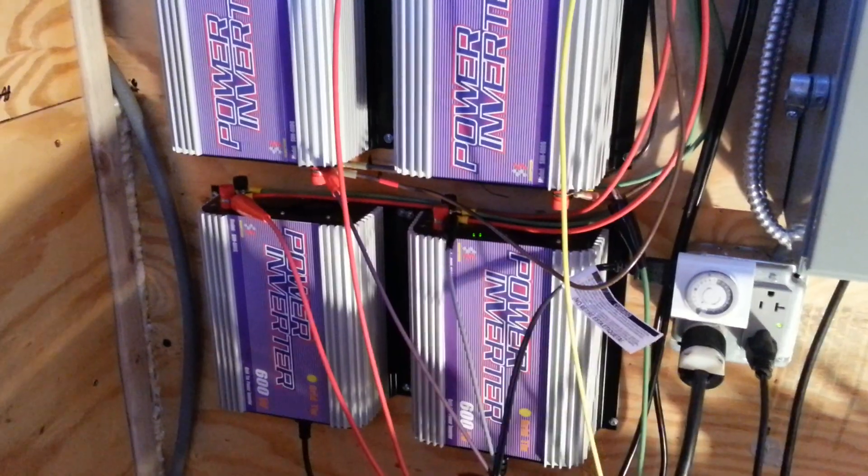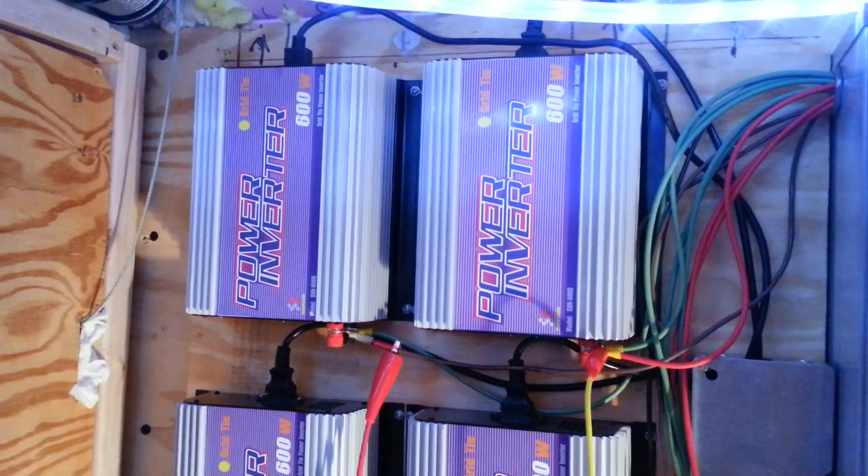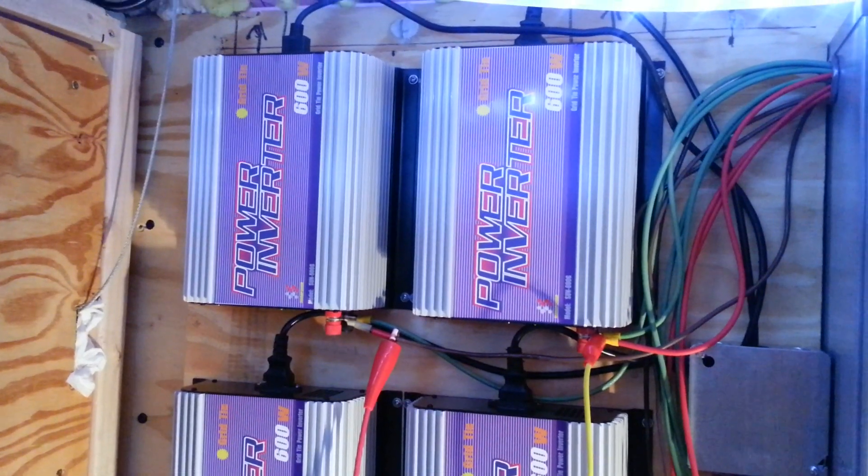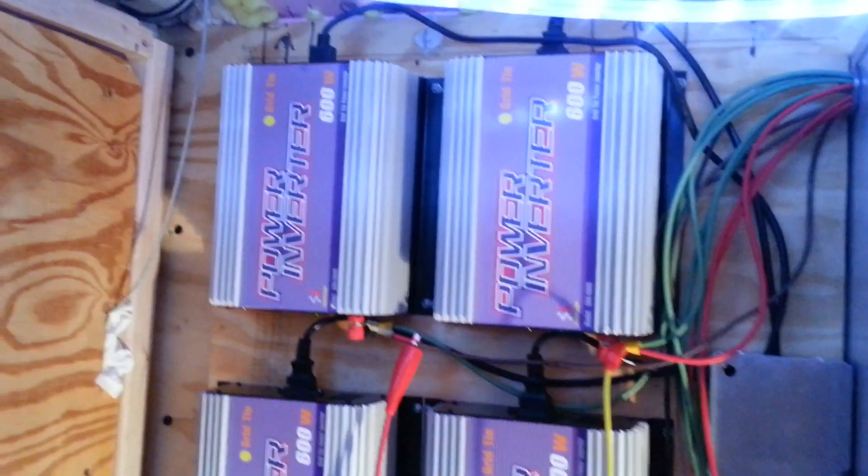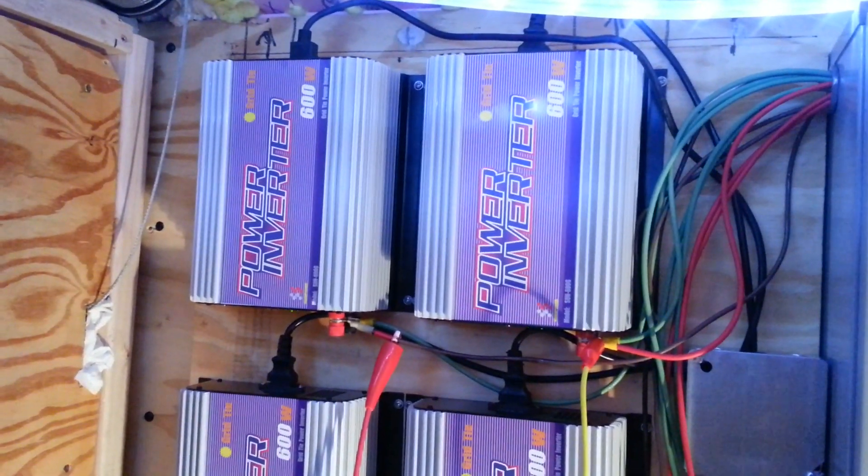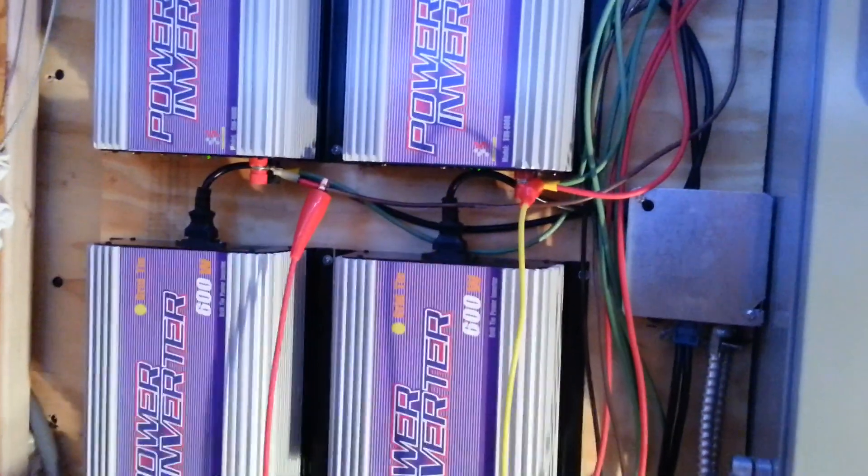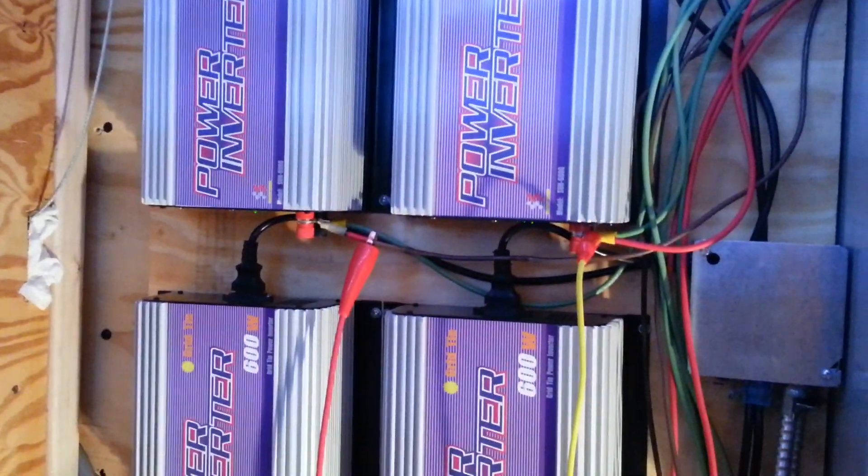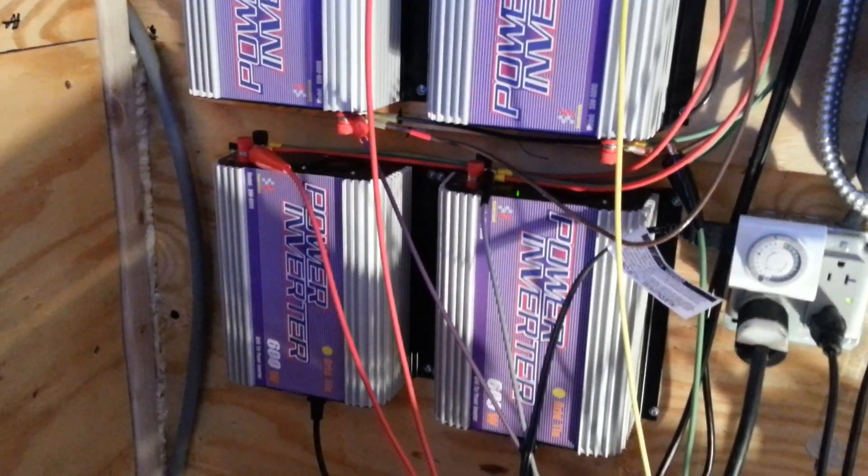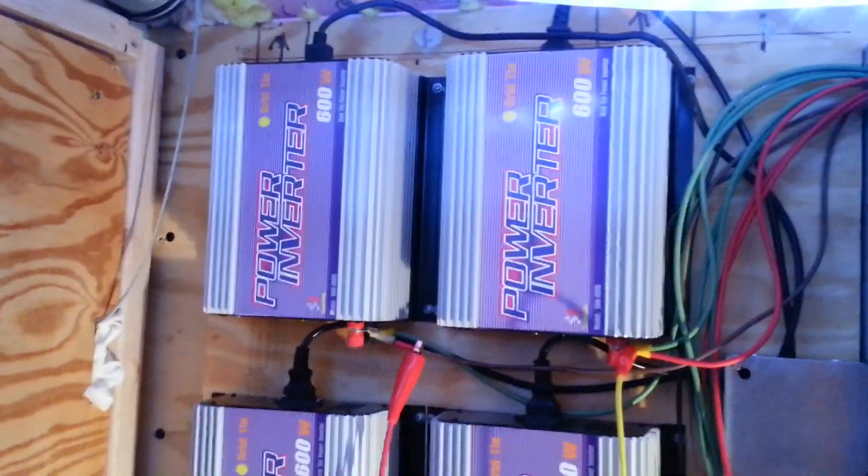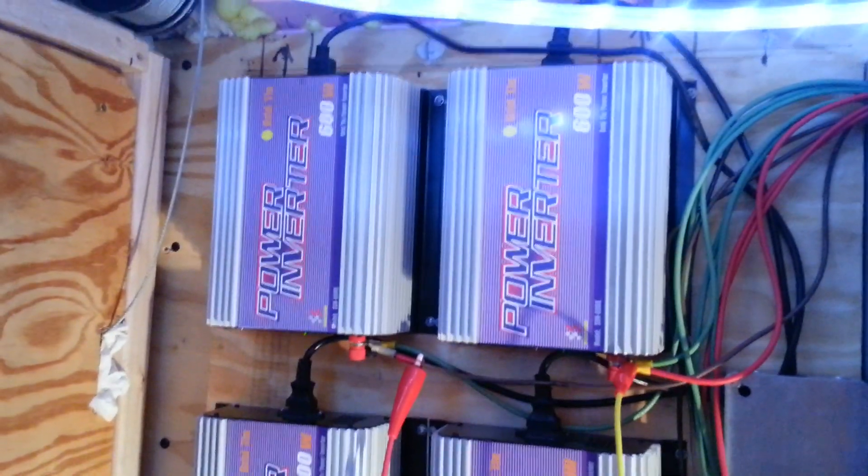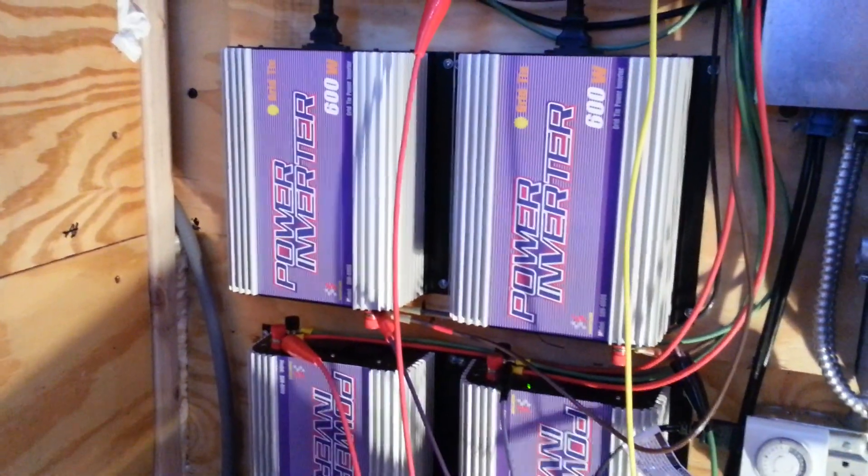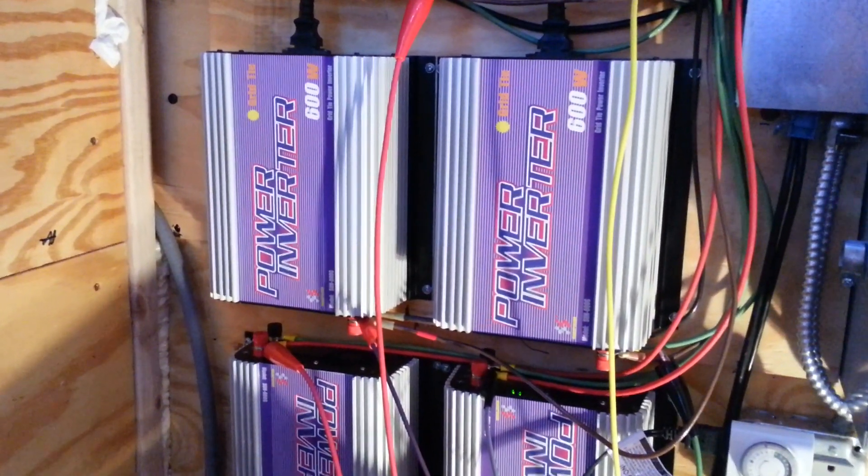One of them per 420-watt panel. Each has maximum power point tracking. The only thing I don't like about them is that you can't remotely monitor them via internet or computer. It's real simple: solar panels in, 120 volts out, very simple, nothing else, and some status LEDs. I like the simplicity but it'd be nice to have the monitoring capability. When you're on a lower budget, a cheaper system, you're not gonna get that. These are very economical: less than $140 shipped a piece, 600 watts a piece, and rated at 22 volts up to 60 volts input.